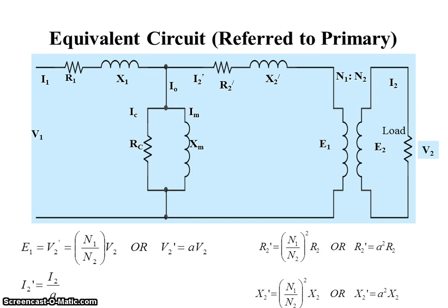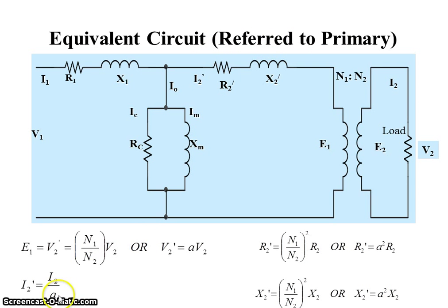The equivalent circuit may be calculated as referred to primary side or referred to secondary side. The equivalent circuit referred to primary side means the secondary parameters will come to the primary side with some changes. V1 is the terminal voltage of primary side, I1 is the primary side current, R1 and X1 are the resistance and reactance of the primary side. R2 dash and X2 dash are the changed values of the secondary parameters. These secondary parameters have values as shown in the equations, using the transformation ratio: V2 dash becomes A·V2, I2 dash becomes I2/A, R2 dash becomes A²R2, and X2 dash becomes A²X2, where A is the transformation ratio.